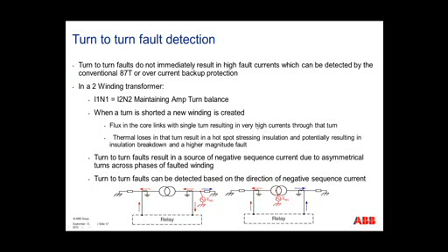So turn-to-turn fault detection. The way this works, let's move down to these pictures at the bottom. If we have a fault outside the transformer, the negative sequence currents leaving this fault will go through the transformer, through this CT, out this CT, giving us essentially a balanced differential for negative sequence currents. However, when we have a fault inside the transformer, the transformer itself becomes a source of negative sequence currents. The currents would leave the transformer. The relay itself would see a net negative sequence current and trip, indicating that you have a winding failure inside the transformer.